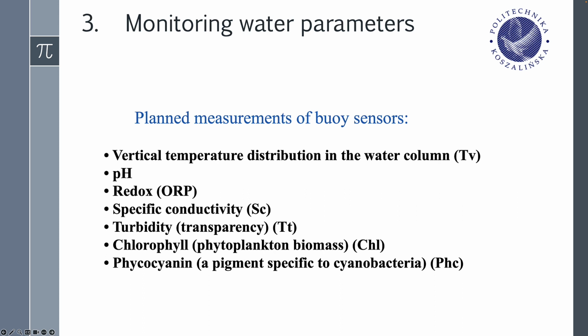Phycocyanin, a pigment specific to cyanobacteria, PHC. An important parameter in warm periods when the reservoir is used for recreational purposes. An increase in this parameter may indicate an approaching moment of cyanobacterial blooms, an early warning system. The measurement is carried out in a manner analogous to the chlorophyll measurement, using an LED emitting light with a specific wavelength, 620 nm, and a detector, 650 nm.